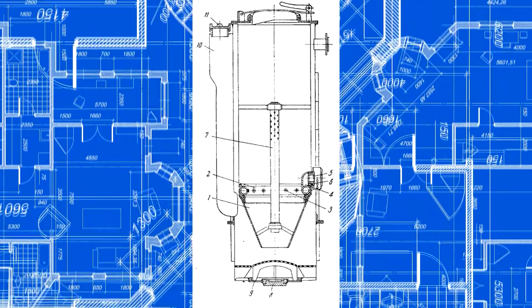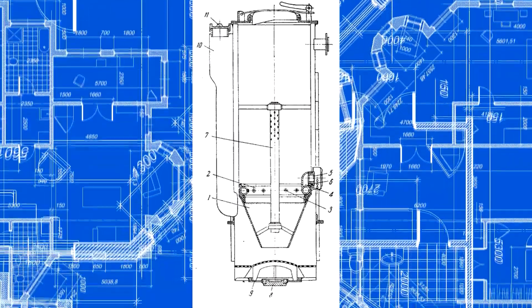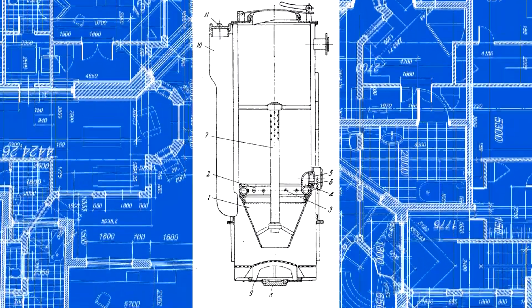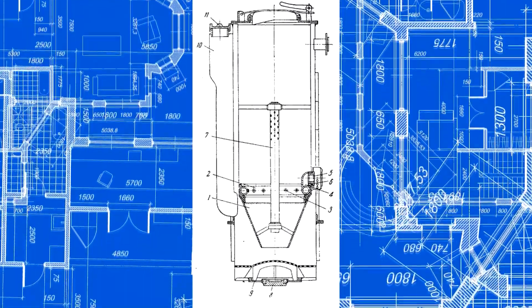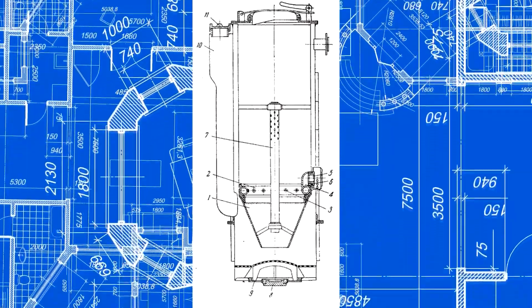Note that the pipe is not located outside the gasification chamber, but is slightly higher, so that water and tar vapors pass the zone of glowing coals in which there is no more oxygen because it has burned above. Thus, the high-caloric gases are not burned but go further to the engine through filters.